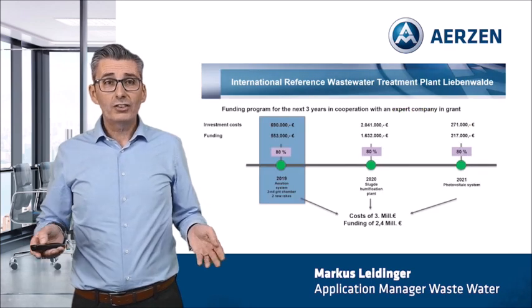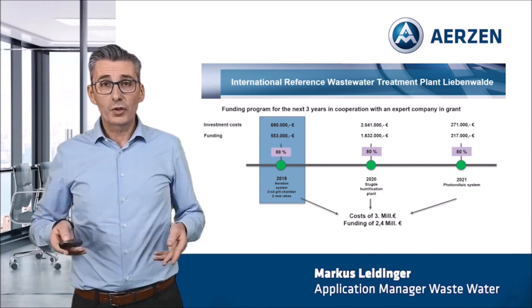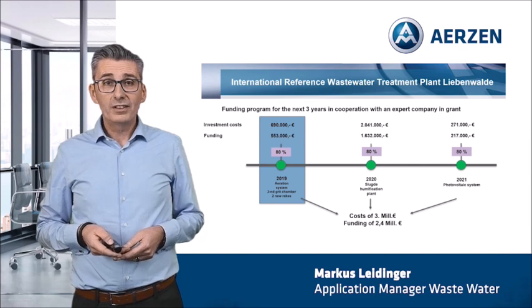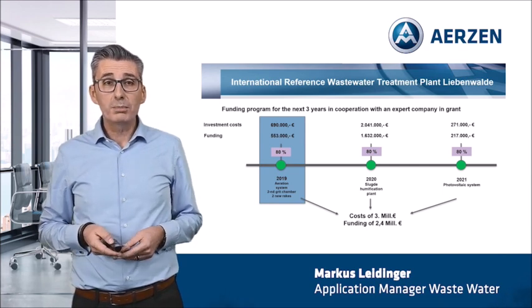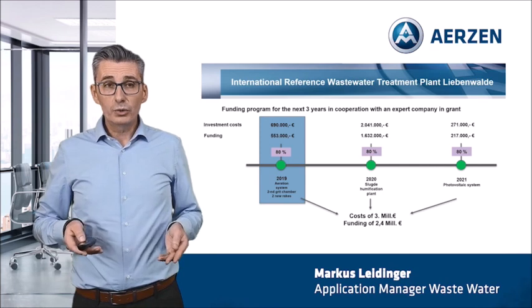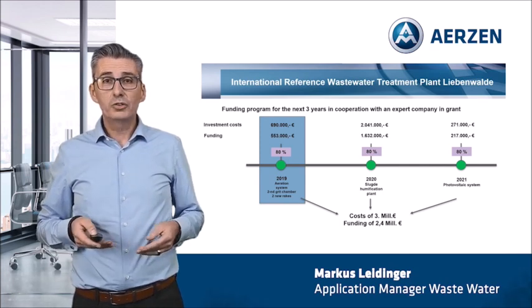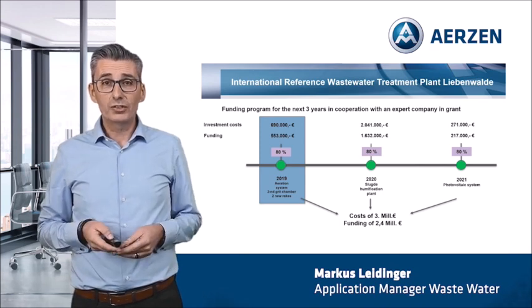What was the solution? Together with an expert company for grant application, we were able to secure a funding program. Within three years, three different treatment processes were completely rebuilt. We started in 2019 with a new fine bubble aeration system, inclusive new rotary piston compressors, a second grit chamber and two new rakes. The investment cost amounted to 700,000 Euro.